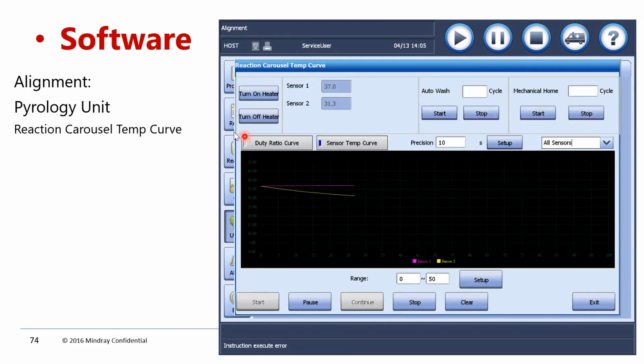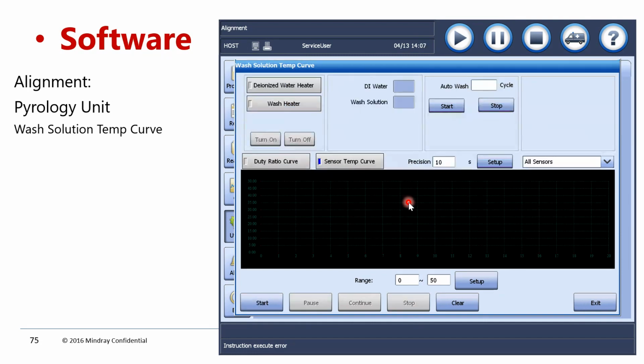And coming to pyrology, in the pyrology unit, you have two options: reaction carousel temperature you can check, as well as reagent compartment temperature you can verify. So here you can turn on the heaters, you can verify the sensor feedback signal. By seeing this, you will come to know whether temperature is stable or not. So two sensors will give feedback signal to the board. Based on that, power is applied to the heaters. And this is for the water heater and wash water heater. So as we discussed, 45 degrees it is supposed to maintain. So we can see how these heaters are working.